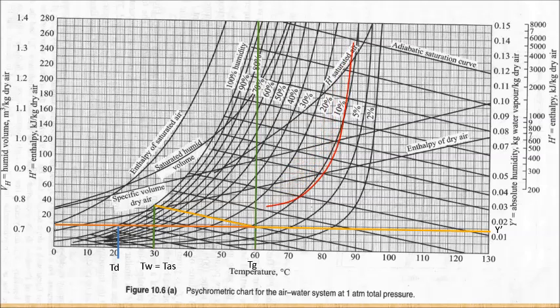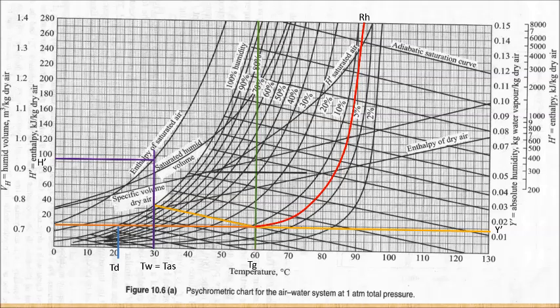At that point as well, the relative humidity can be obtained as approximately 9%. For the enthalpy and humid volume, draw a vertical line from the wet bulb temperature until it meets both the enthalpy of saturated air and the saturated humid volume line. Drag a line to the left axis to obtain enthalpy equal to 94.2 kJ per kg dry air, and another line further left to get humid volume equal to 0.891 m³ per kg dry air.